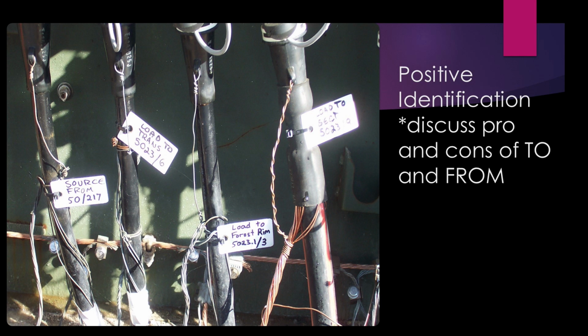Also be wary of getting into to and from, especially if you have loop feeds. If you're not just a radial fed system, to and from can get changed up real fast. It's a good idea to label it T1, T2, or J1, J2, something like that. That way if you go source to load, it always goes from T1 to T2. If you do to and from and you backfeed it, the from becomes the to and the to becomes the from. That kind of confusion at 2 o'clock in the morning with a guy unfamiliar with it can only spell disaster. Make sure everybody's on the same page as far as that goes.